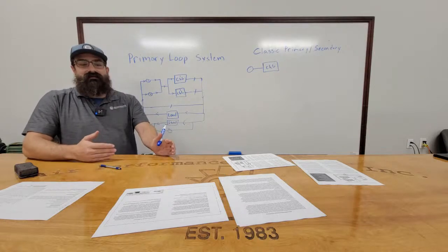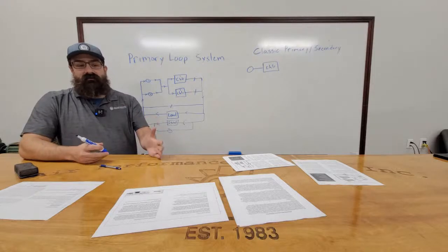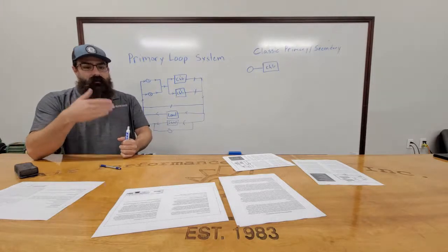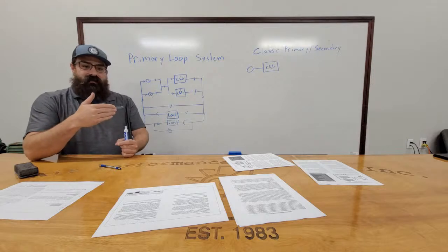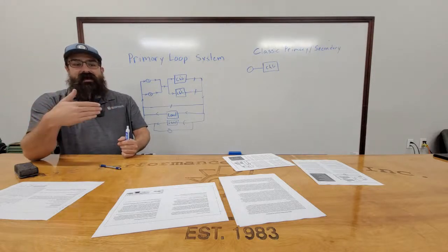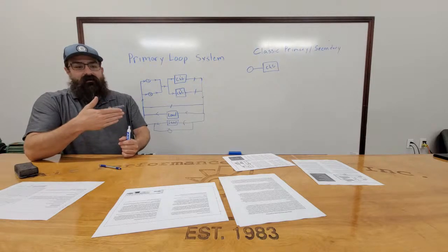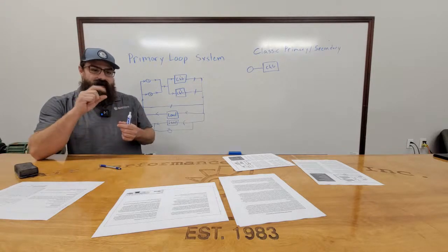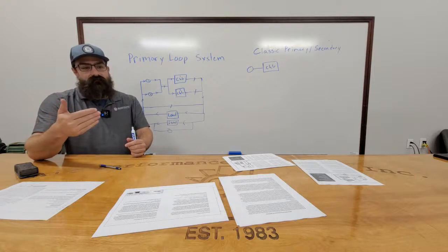But we've had issues where the ISO valve won't close or doesn't close. But in this particular setup, there are butterfly valves that have been set by the chiller startup tech because the chillers have flow meters inside of them. So they've closed the valves manually and then put a nut and a bolt in them to lock them in place to set the flow through the chillers.